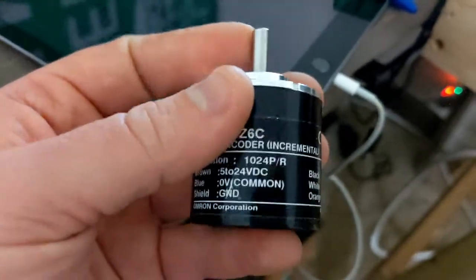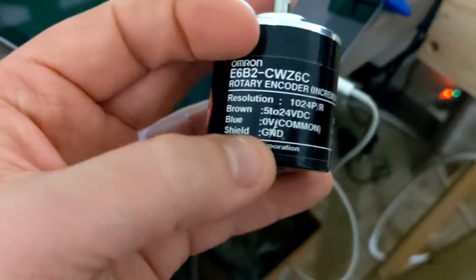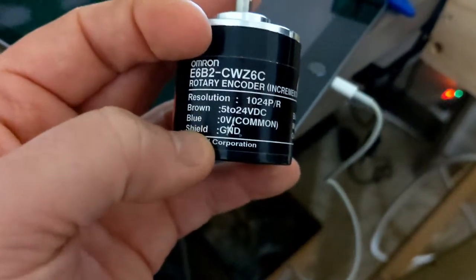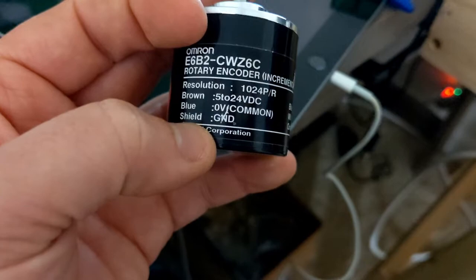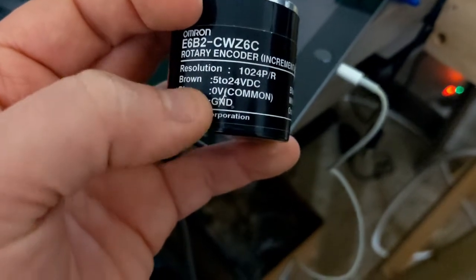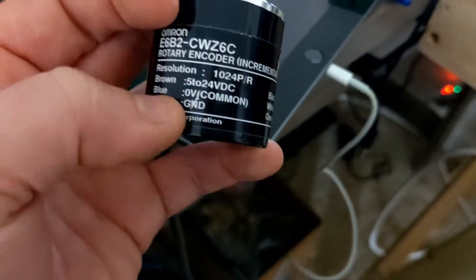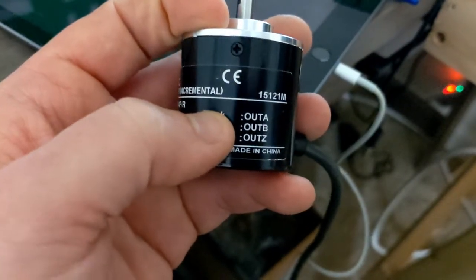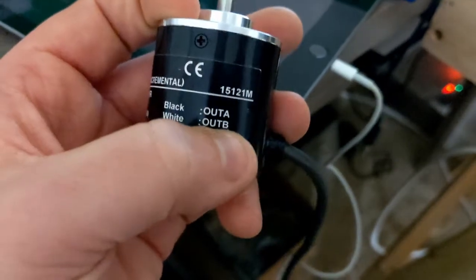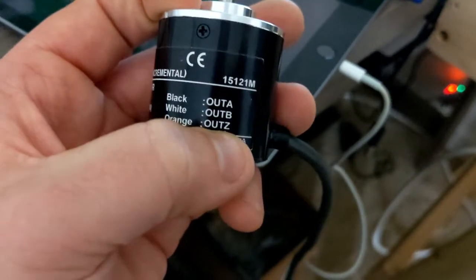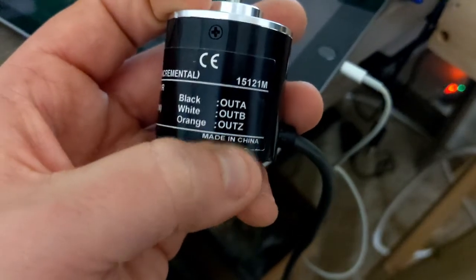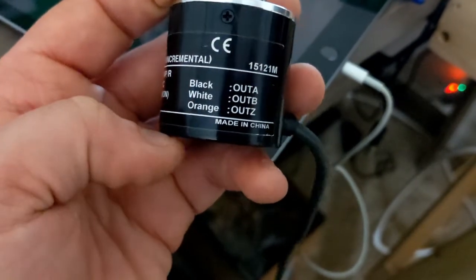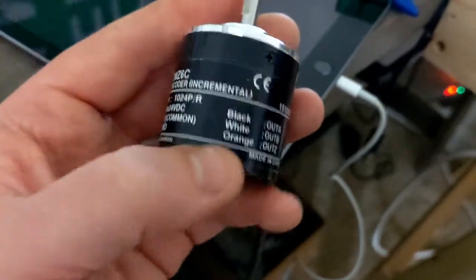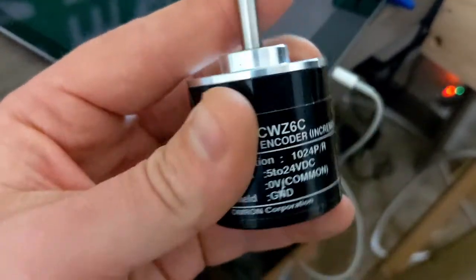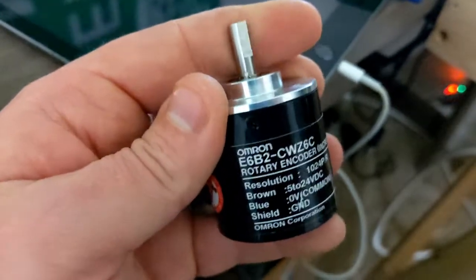So, let me show you exactly what I'm talking about here. It's got 6 cables if you're including the shield, so it's a 5 cable connection. It's got a brown, which is your voltage, and a blue, which is your common. It has your black, which is your A output, white is your B output, and your orange, which I'm coming to find out you don't need to plug in anywhere. That's just a signal that goes back saying that it's working, in case you had a failure on this.